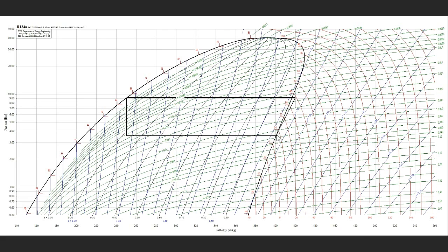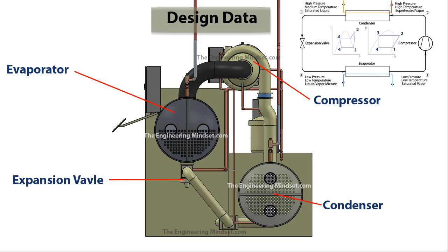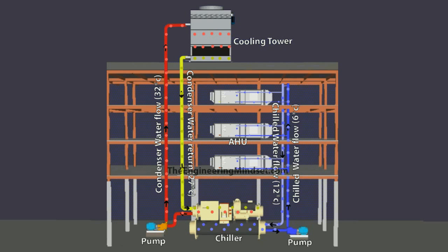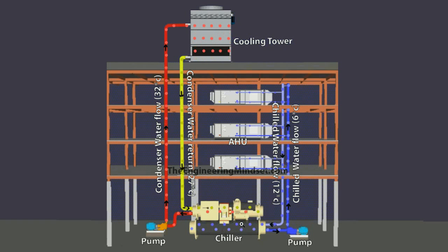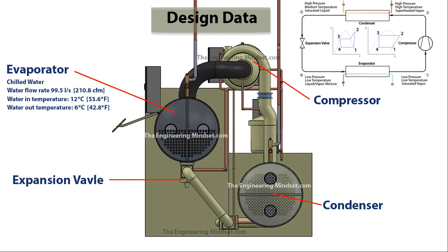We are going to look at the data points at all four points — one, two, three, and four. Before we look at the refrigerant properties, let's look at what's happening with the water through the evaporator and condenser. In the evaporator, the chilled water is cycled — it rises through the risers out to the AHUs and comes back carrying the unwanted heat from the building. In this example, the water is flowing at around 99.5 liters per second, approximately 210 cubic feet per minute. The water returns at around 12°C (53.6°F) and leaves the evaporator at around 6°C (42.8°F) after dumping its heat.